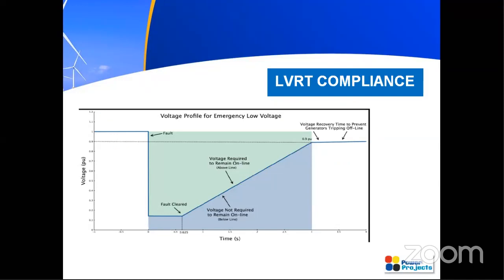Coming to a very important point, LVRT compliance. LVRT is low voltage ride through. Low voltage ride through compliance is a very important one. We have two things: one is LVRT and another is HVRT, that is, low voltage ride through and high voltage ride through. From the name itself, we can get an idea that our wind farms integrated with the grid have to ride through this low voltage or high voltage.